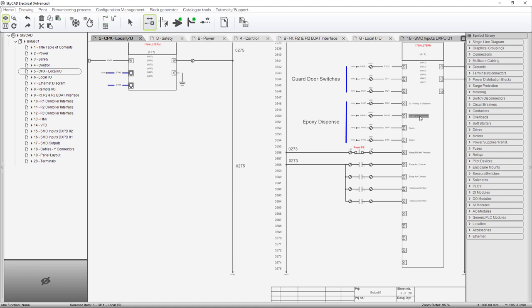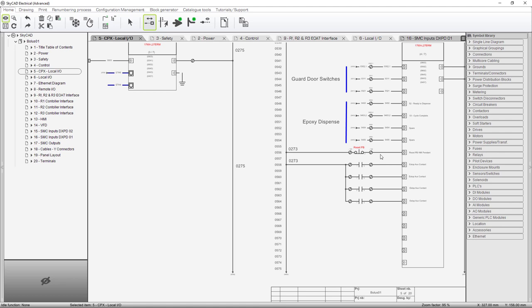Here we have the reset push button, but notice we're using the normally closed. We use the normally open to reset the safety system and then we're using the other contact block on that reset button and it's a blue lit push button. We're using the normally closed as an input to the PLC saying that the reset button has been pushed. Now if you know your programming, you know, normally open, normally closed. When it comes to logic, it doesn't matter. You just examine it or read it and if it's on, it does one thing. If it's off, you can do something else. So in this case, if this input goes off, we know somebody pushed the button.